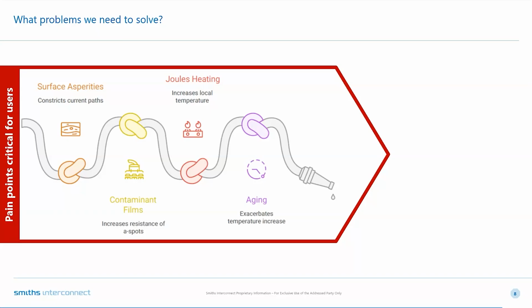When current is forced through these small points, you create joule heating, which then gets exacerbated by aging through thermal cycling, vibration, and material degradation. All of these things are at play to turn what seems like a good connector on day one into a poorly performing connector after a few years in operation. This is what one has to be mindful of.